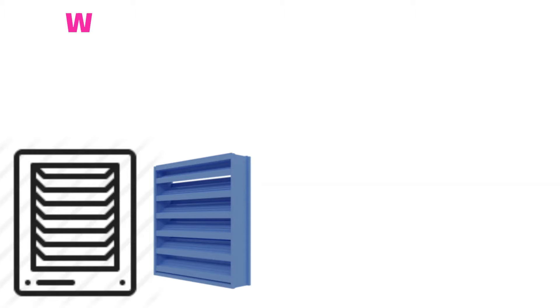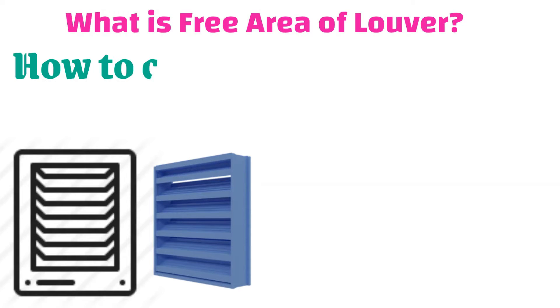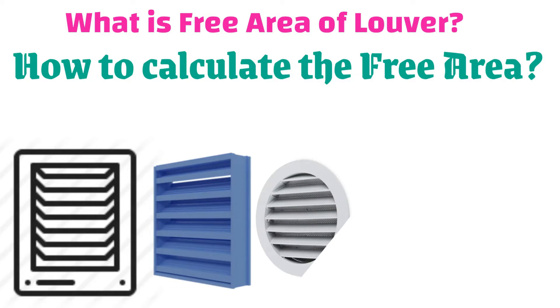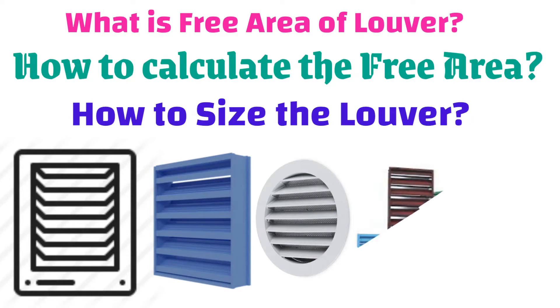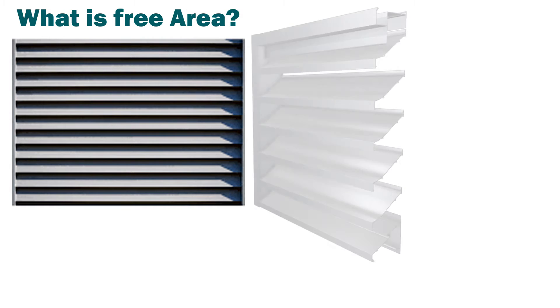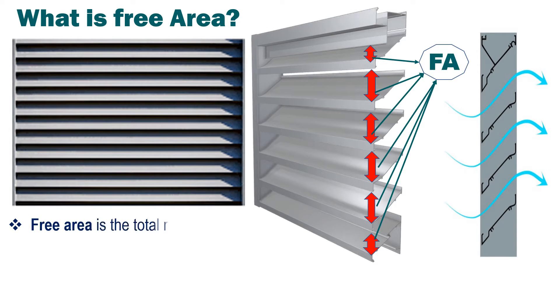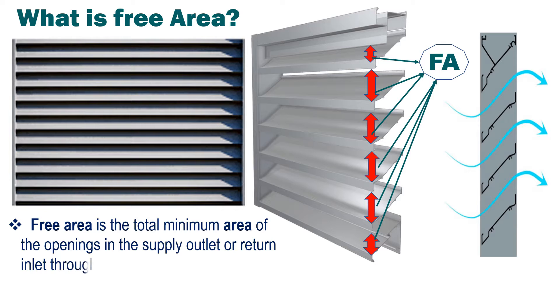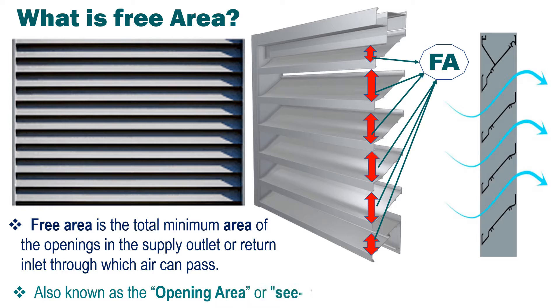Hi friends, welcome to HVACR Engineers. In the previous video we understood about face area, free area, core area, and effective area of a louver. This video is to understand how to calculate the free area of a louver and how to size the louver. First, we need to understand what free area is. Free area is the total minimum area of the openings in the supply outlet or return inlet through which air can pass. It is also known as the opening area or see-through area of a louver.